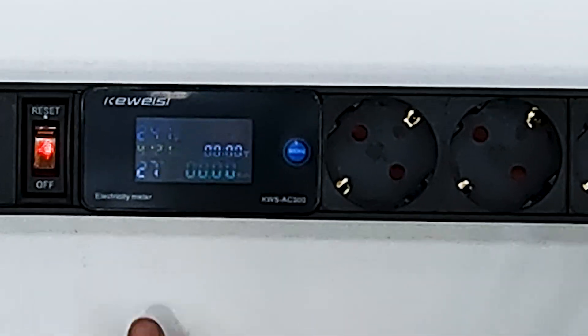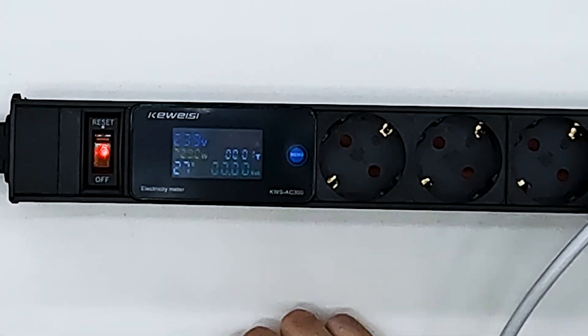It is showing the correct value. Let's connect the second heater — the second device should consume around 400 watts on the first mode and around 800 watts on the second mode. We're seeing 414, 410, 408 watts — the correct value as expected. On the second mode: 814, 813, 808 watts — also correct. Let's turn on both devices at the same time: 1200 watts right now. When turned off: zero watts.